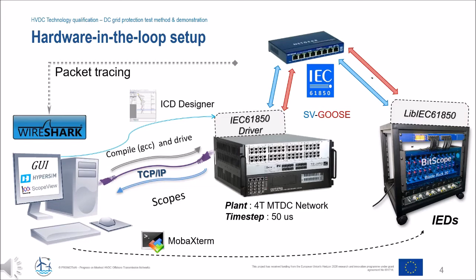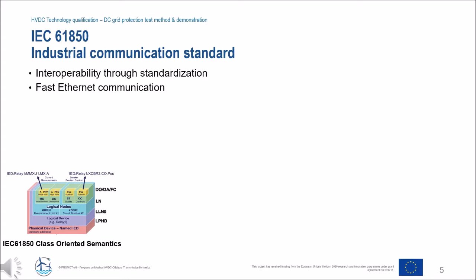Data exchange was done through the IEC 61850 communication standard, which is meant to create an interoperable environment in digital substations. It is also considered a fast Ethernet protocol, which allowed us to obtain satisfactory performances in terms of speed for the non-selective protection strategies.